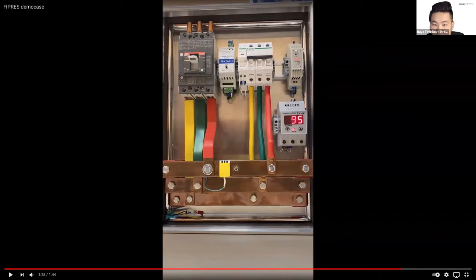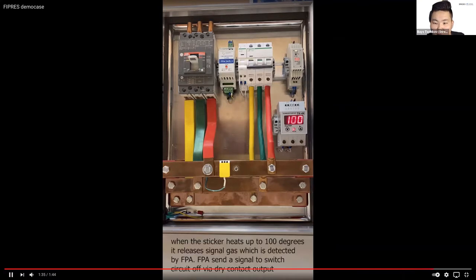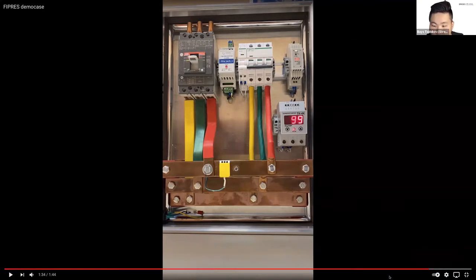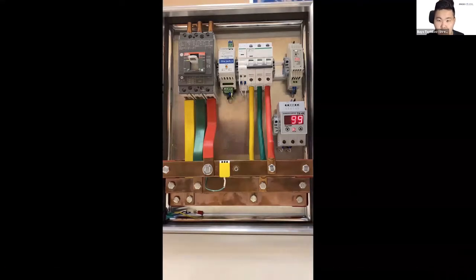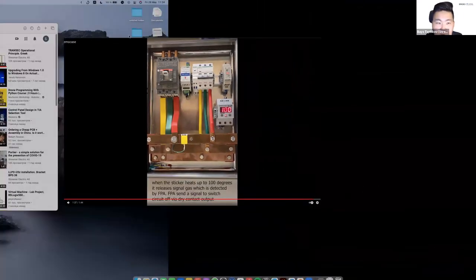You can see here that the FPA is glowing green. The LED indicator is green, which means the FPA is in standby mode. And as soon as it detects a decent amount of signal gas, it changes the color to red, which means the alarm mode has been activated. The dry contact output closes, and the circuit breaker should switch off. You see, at 99, when the sticker heats up to 100 degrees, the signal gas goes out and the FPA triggers and switches off the circuit breaker. Let's check it again. It happened at 99. Yep, that's how it works, the example of operation.